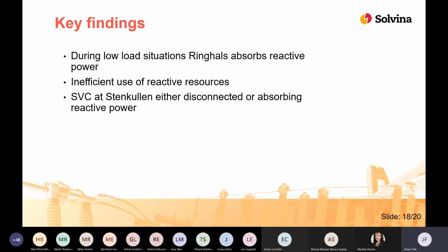Some key findings from this data we have looked at is that we can see that the reactive power capacity of Ringhals seems to be used to a fairly high degree, both during low and high load situations. We have seen that the reactors in the area at some instances are connected when it might have been more appropriate to have them disconnected, and vice versa. We have also seen that the SVC at Stenkullen, at the instances we have investigated, is either disconnected or absorbing reactive power.